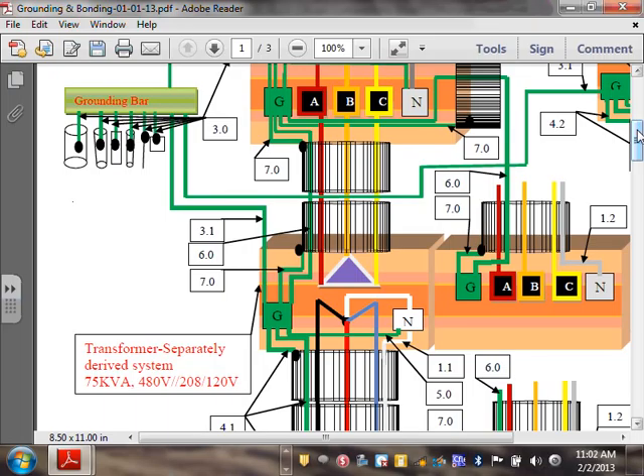If you have a campus, guys, you typically have one service coming to a building, and you shoot feeders from one building to another. If you're the U of M, these feeders will be 13.8. That's how they have their distribution system, 13.8, shooting from one building to another. If you're a small campus, you're 480, and you shoot with a 480 system. Now, do you have to do it this way, by the way? If you have a campus, can you have multiple services coming to your campus? You can. They're different, separate buildings.